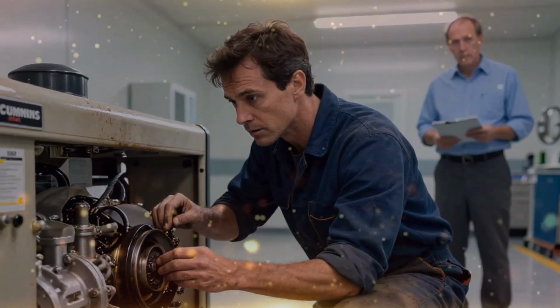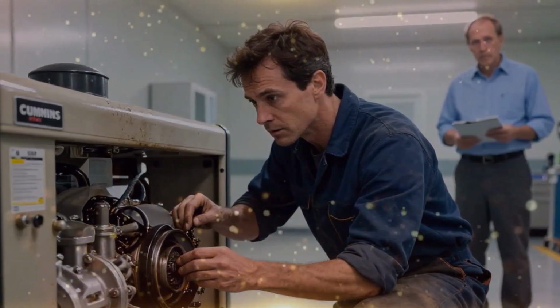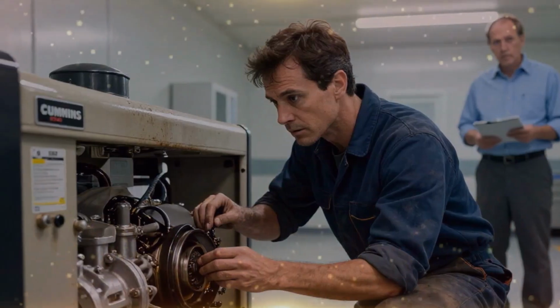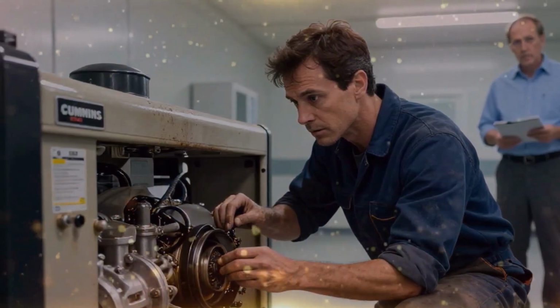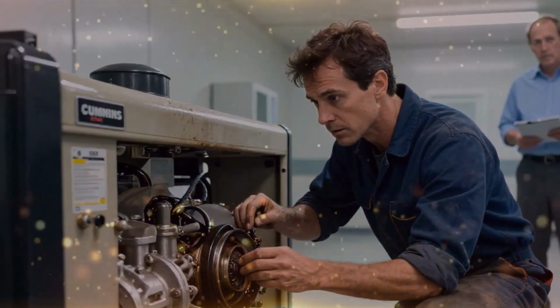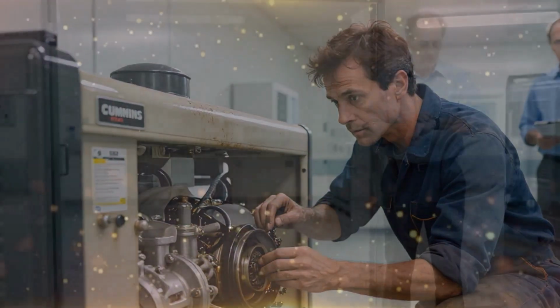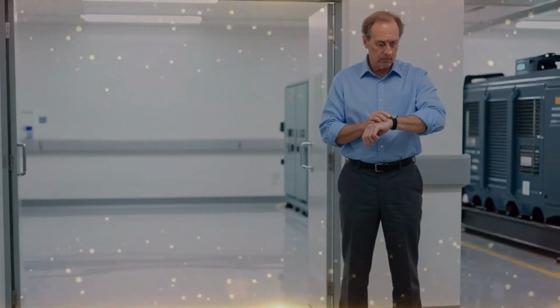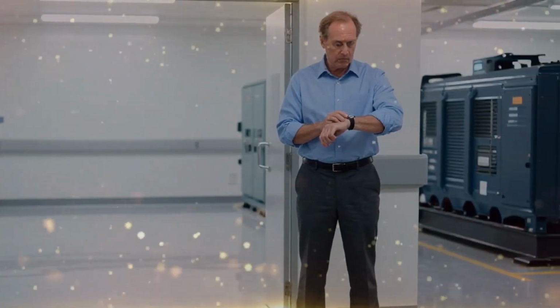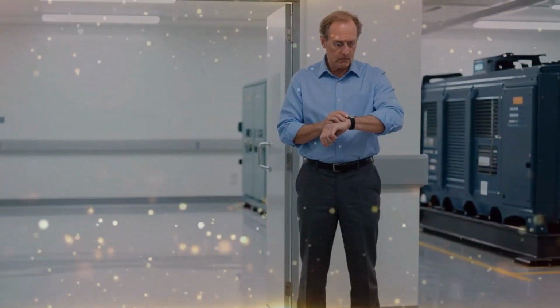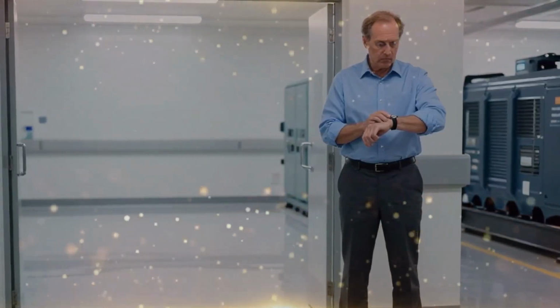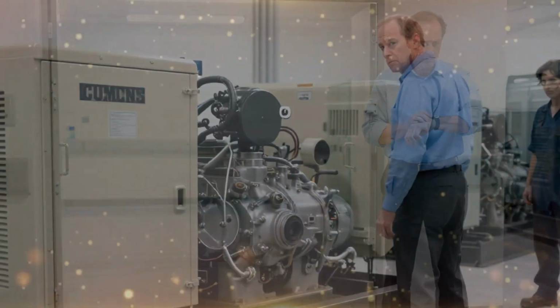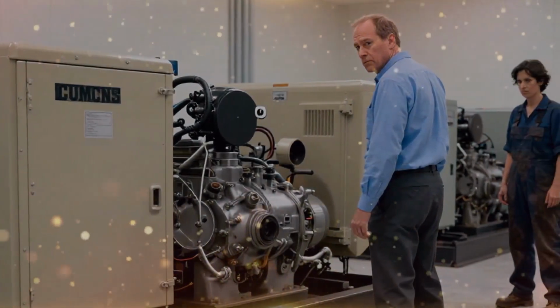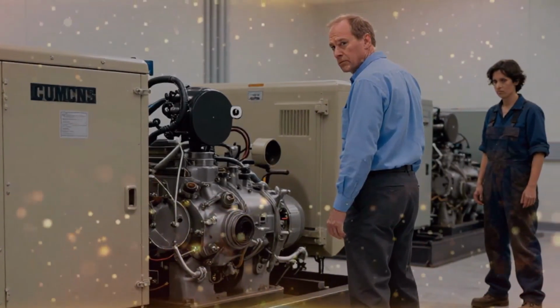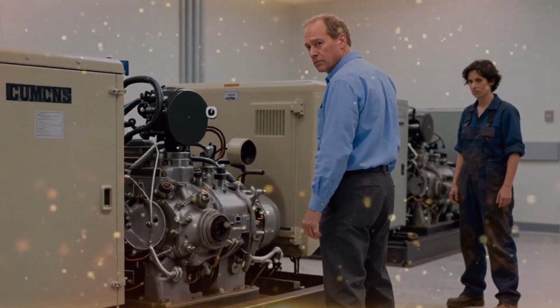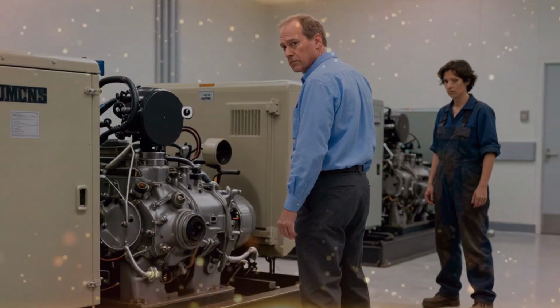The bill on the manager's desk sat at $60,000. For that price, they had purchased nothing but confusion. They had replaced the fuel solenoids because the computer said low pressure. They had replaced the governor control unit because the computer said signal loss. They had even replaced the entire exciter assembly on the back of the alternator. None of it mattered. The machine didn't care about their new electronics because the problem wasn't electronic. It was a fundamental misunderstanding of how a 12-cylinder diesel engine breathes.